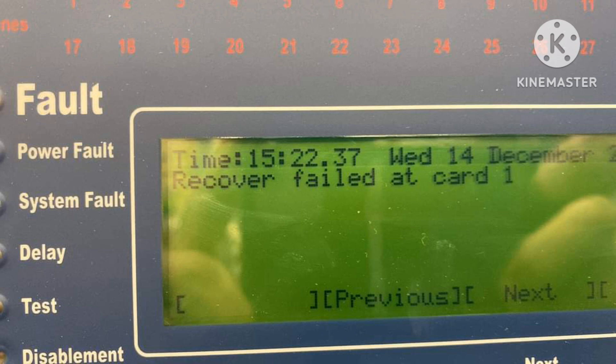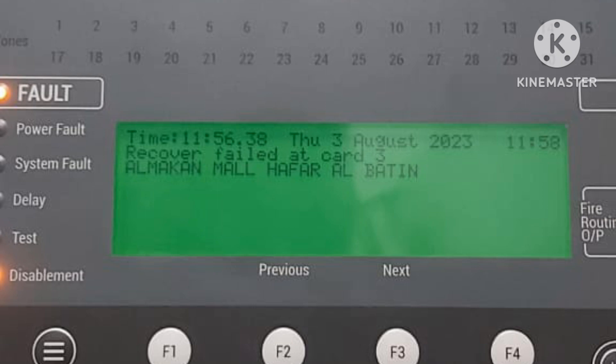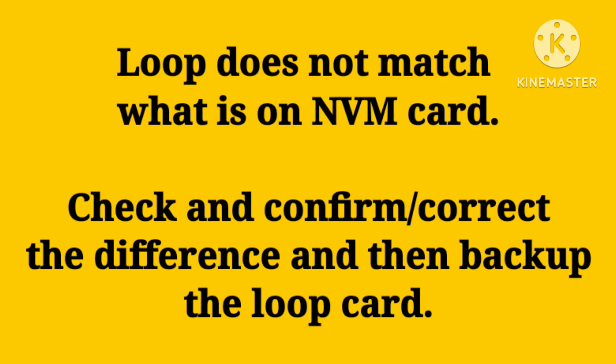If you get a recover fault at card one, first let's understand the reason. 'Recover fault at card three' means the backup has failed, or the NVM is not reading the previous backup. 'No matching' means the loop does not match what is on the NVM card — the previous data doesn't match because something has changed on the loop, such as cables or devices.